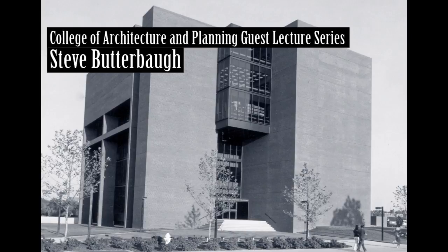What is the order from shortest to longest payback period? In the Army's case, the lights were first, with 10 months. The surgery air handler second, with 3.5 years. The emergency room air handler with 5.6 years, and the replacement windows with 62.3 years.